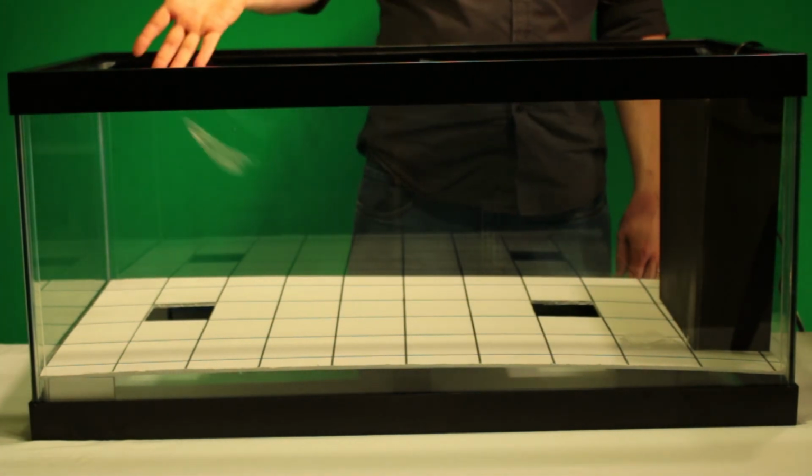So, this is why design guides tend to tell you not to put the CRAC units at the end of the cold aisles. If you do have this particular problem, you can either relocate some of your server racks, or you could install underfloor baffles which redirect the air and allow for proper airflow. Or you could decrease the fan speed of your CRAC units, or you could do a lot of things. The point is that once you know what the problem is, it becomes 1,000,000 times easier to solve it.